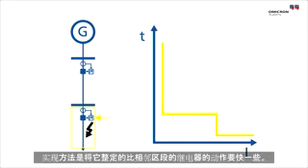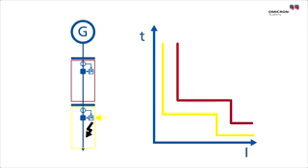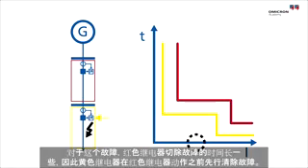This is achieved by setting it to work faster than the relay in the neighboring segment. For a specific fault current, the red relay would have a longer time to clear a fault, so the yellow relay clears it first, and so the fault is cleared before the red relay would react.